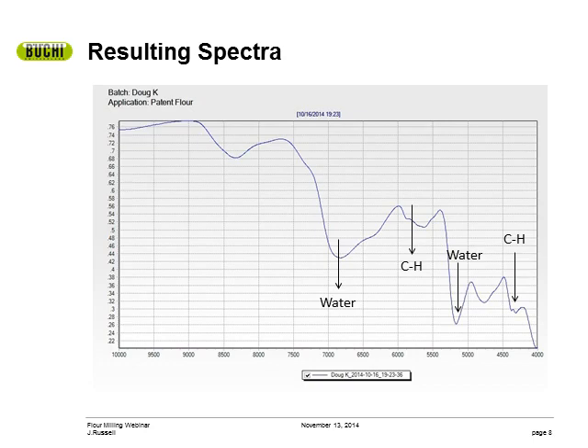Here is a beautiful spectra of a flour sample. You can see that the whole spectra is dominated by the water bands with large water peaks. There is also protein information in there, although it is not as visually defined. Fat is recognized by the CH bands. The spectra is what I call rolling hills and valleys — you cannot easily see varying concentrations of moisture and protein. We have to use sophisticated mathematics, or what we call chemometrics, to extract the information and develop the linear calibration. Buchi typically does this part for you, unless you want to do the chemometrics yourself.